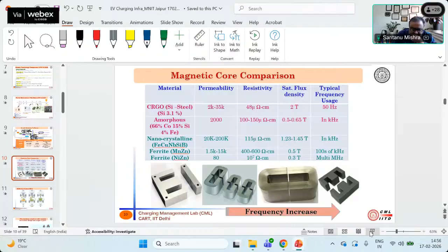So regarding magnetic size, let me point this out. Normally at 50 hertz we use CRGO, like iron core. At slightly higher frequency we go for amorphous core and nanocrystalline core. These are actually very modern designs, popular in high power chargers like 800 kilowatt or 500 kilowatt. Then ferrite core is popular at hundreds of kilohertz, and nickel zinc is popular at the megahertz level. So this is the mapping of your cores.